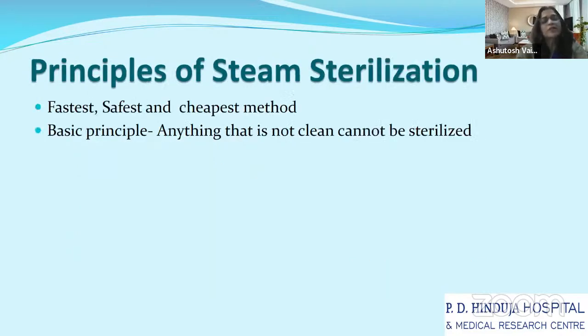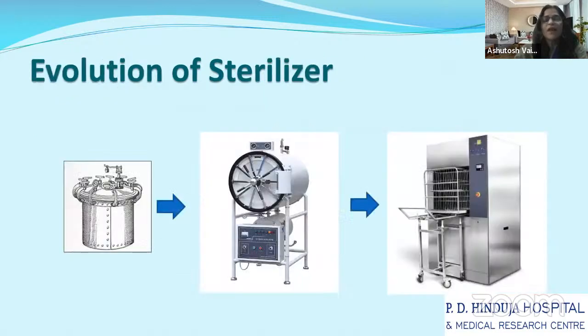Moving towards the principles of steam sterilization. We all know that steam is the fastest, cheapest, and safest mode of sterilization, readily available, very safe and very fast. Now, a basic principle in any kind of sterilization is that anything which is not clean cannot be sterilized. So the baseline we should remember is that sterilization must have basic cleaning processes done perfectly. Only then can we achieve sterilization.